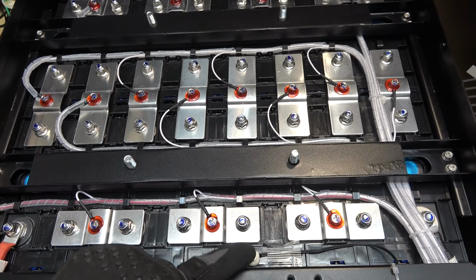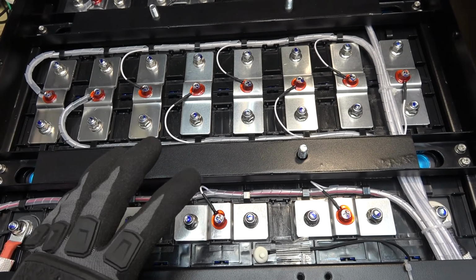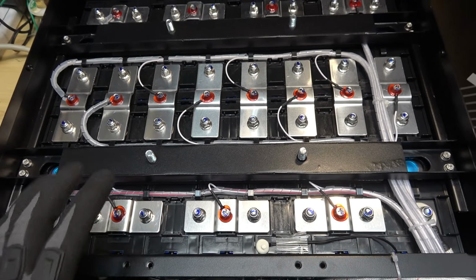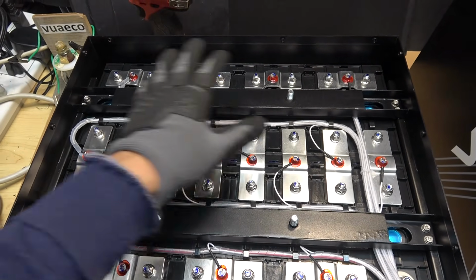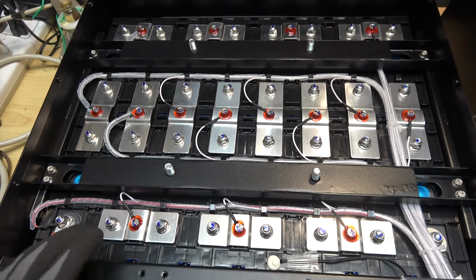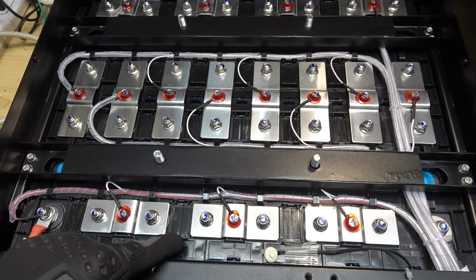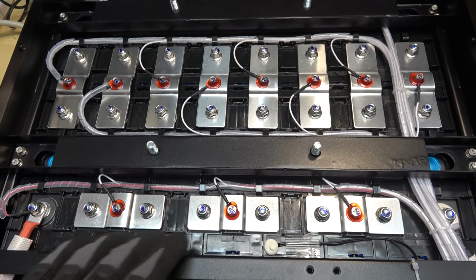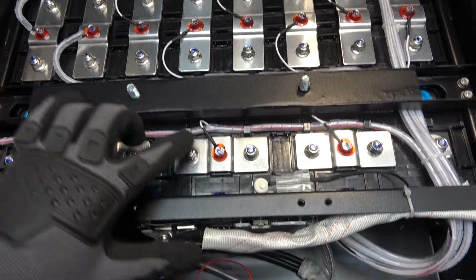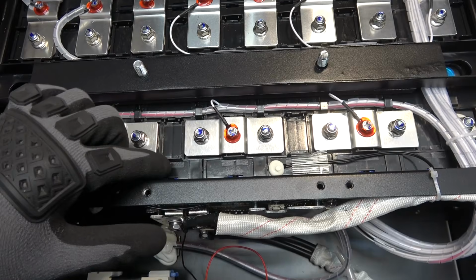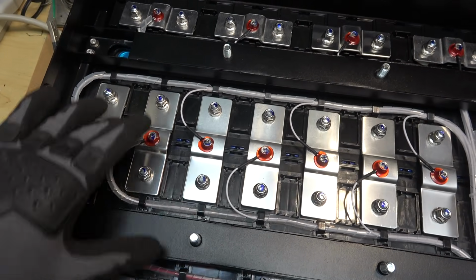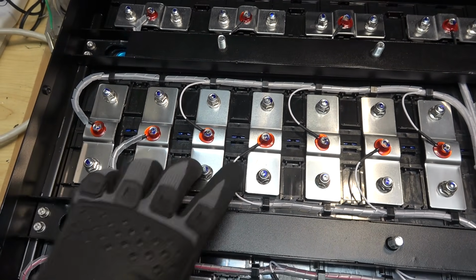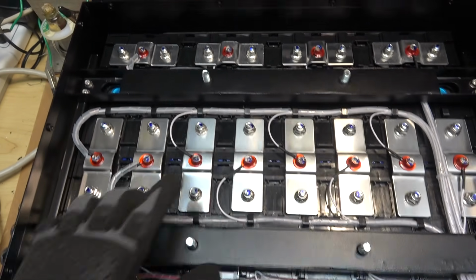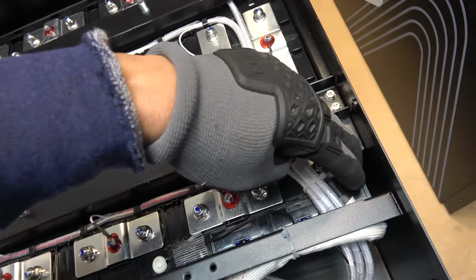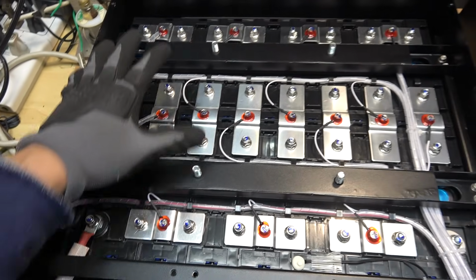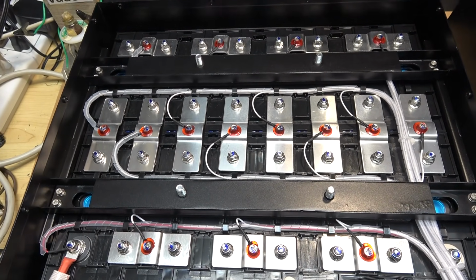The reason this heat sensor is not glued onto the actual battery cell is because the entire battery inside here is encased inside plastic insulation. You can see it's between the aluminum bus bar and the actual cell. All of this black part here is plastic insulation, and it's not just on the top, it's also on the side too. So it's all the way around the entire battery pack.